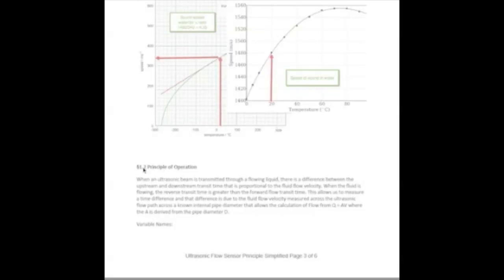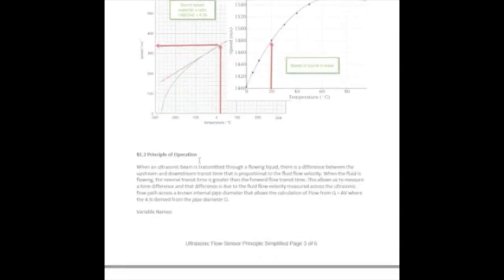And I get this because people get confused about how these things work. They confuse them with magmeters. They're not anything like a magmeter. Magmeter requires electrically conductive material. This requires acoustically conductive material. It's like the way bats fly.